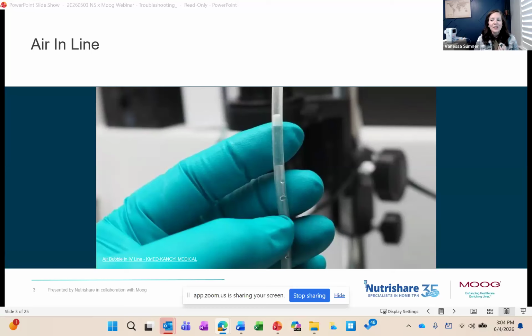The first alarm I want to talk about is the air in line alarm. I'm sure you've all had one. This is where the pump has detected excess air in the tubing. Depending on the pump and its sensors, this could be one big air bubble, or it could be a buildup of multiple air bubbles.